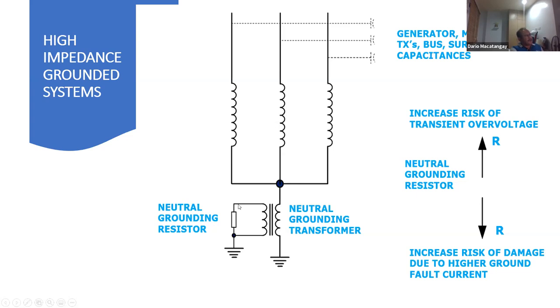Now, using a 59N, you can only protect from this 100% down to a certain portion, let's say 95%. If there's a fault immediately at the 100%, it will trip. If you have a fault at the middle, it will trip. If you have a fault at, let's say, 80%, it will trip. But if you have a fault very close to the neutral, it will not trip, because it can only see the voltage when the fault is within this range. This voltage is dependent on the location of the fault.